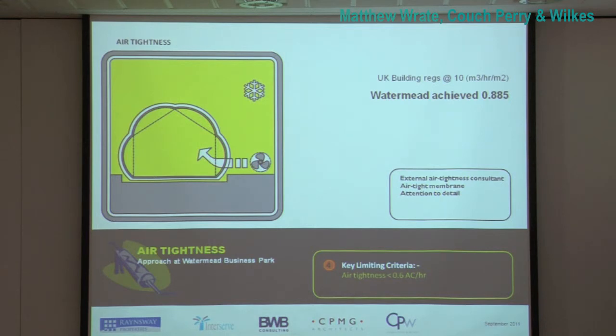Some key aspects in achieving that air tightness: they appointed an air tightness consultant very early in the project. One of the main rules they left with us was that every drawing was to have the air tightness line marked on it—sort of common sense, but it made a big difference putting a red line through all the architect's drawings, which could then be put onto the services drawings.